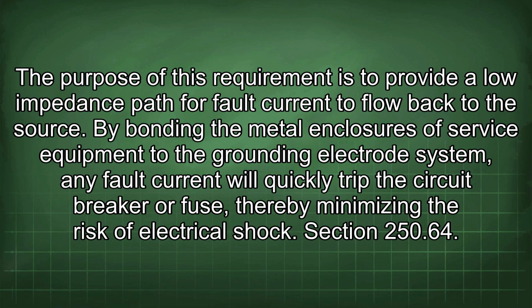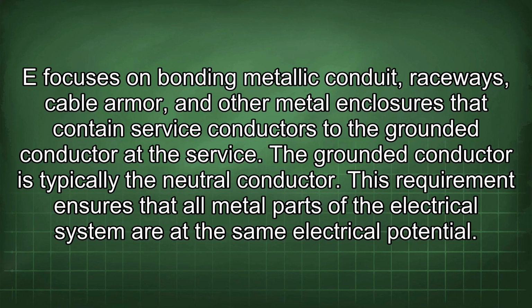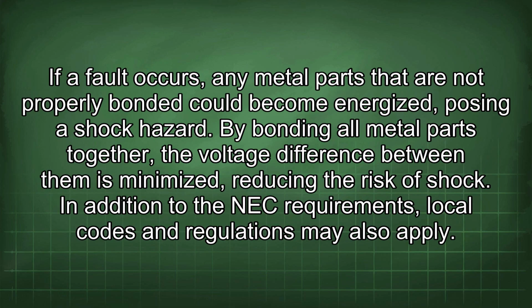Section 250.64(E) focuses on bonding metallic conduit, raceways, cable armor, and other metal enclosures that contain service conductors to the grounded conductor at the service. The grounded conductor is typically the neutral conductor. This requirement ensures that all metal parts of the electrical system are at the same electrical potential. If a fault occurs, any metal parts that are not properly bonded could become energized, posing a shock hazard. By bonding all metal parts together, the voltage difference between them is minimized, reducing the risk of shock. In addition to the NEC requirements, local codes and regulations may also apply.